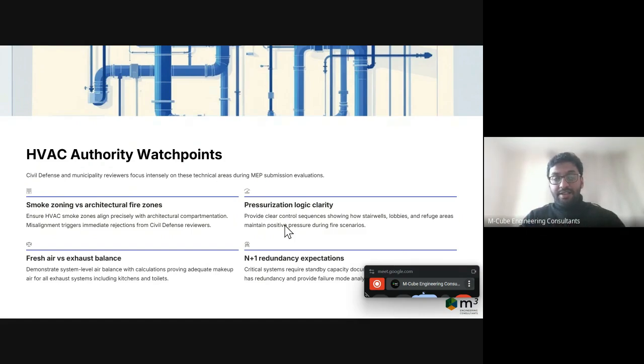As per the Dubai Building Code, flats and apartments generally need to be positively pressurized, and the overall building also needs to be positively pressurized. This can only be achieved when your individual apartments are positively pressurized. So this is something you need to look for in the HVAC design.